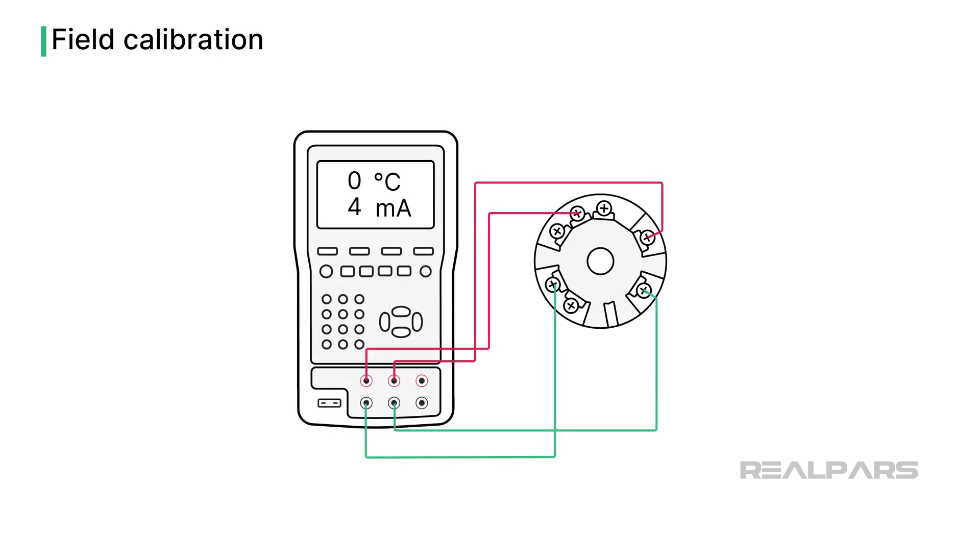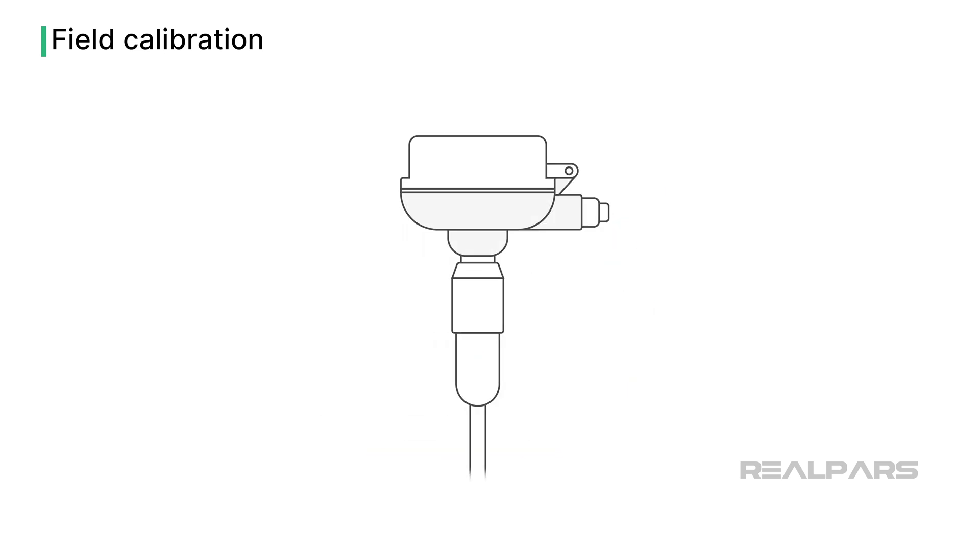Stepping back, we had previously calibrated and adjusted the transmitter, assuming that the process calibrator exactly simulated the RTD characteristics across the entire input range. That exact simulation may not be the case, as the sensor has unique characteristics.